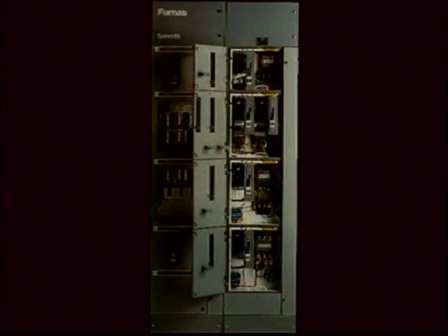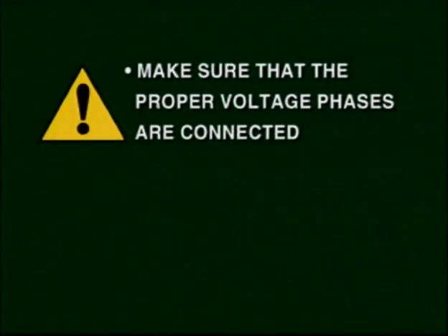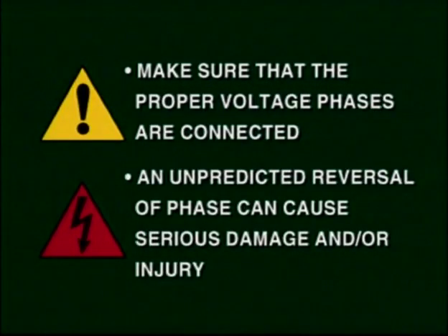The wiring connections made during installation of a motor starter must follow the manufacturer's wiring diagram specifications. As we know, ladder diagram descriptions will serve little purpose, if any, during the wiring and installation of a motor starter. Many times, especially in applications requiring multiple motors to control a line, all starters are housed in motor control centers where they are easily accessed and available for troubleshooting. Of most importance during the installation is to make sure that the proper voltage phases are connected to the proper terminals. Remember that the reversal of phases can cause a motor to change rotation direction, and during startup, this could cause damage to the equipment or injury to personnel.